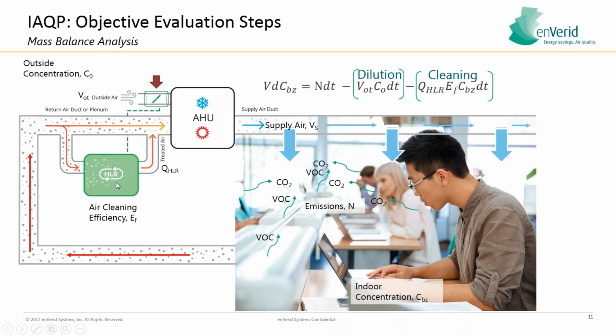We'll break it down. So basically, what is enVerid? In this particular case, an enVerid HLR, or HVAC Load Reduction technology, will be applied to the return air stream of an HVAC system. We're a side stream application, so we actually only scrub a very small portion of the return, and we treat that air for all contaminants and then return that clean air back into the system's return to the air handler, and all your downstream systems can remain constant.